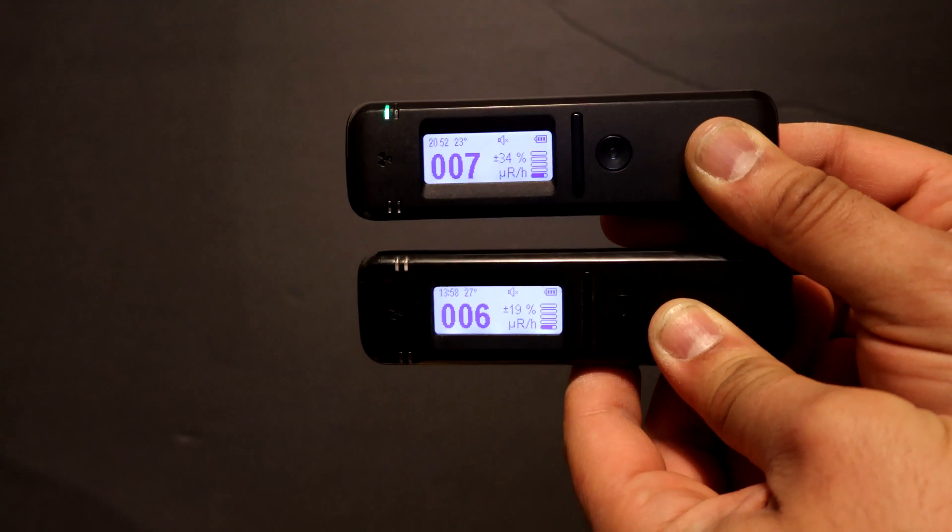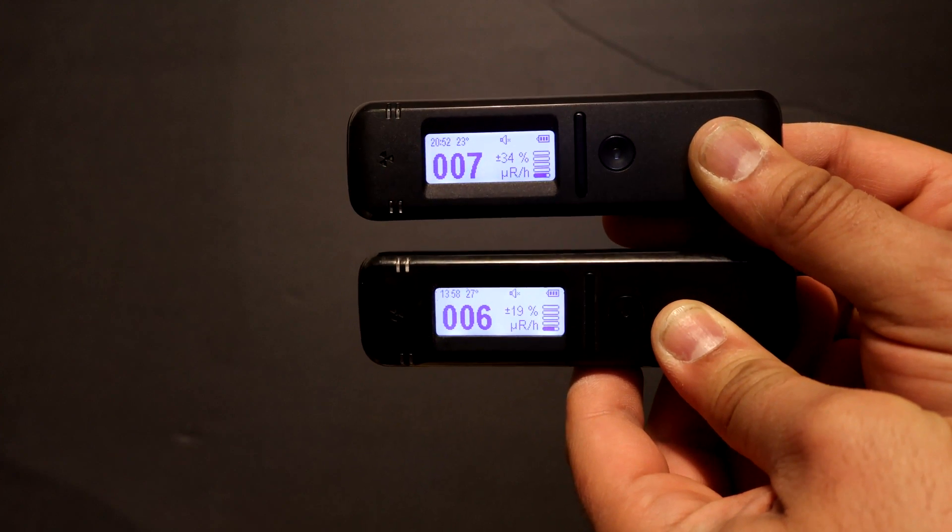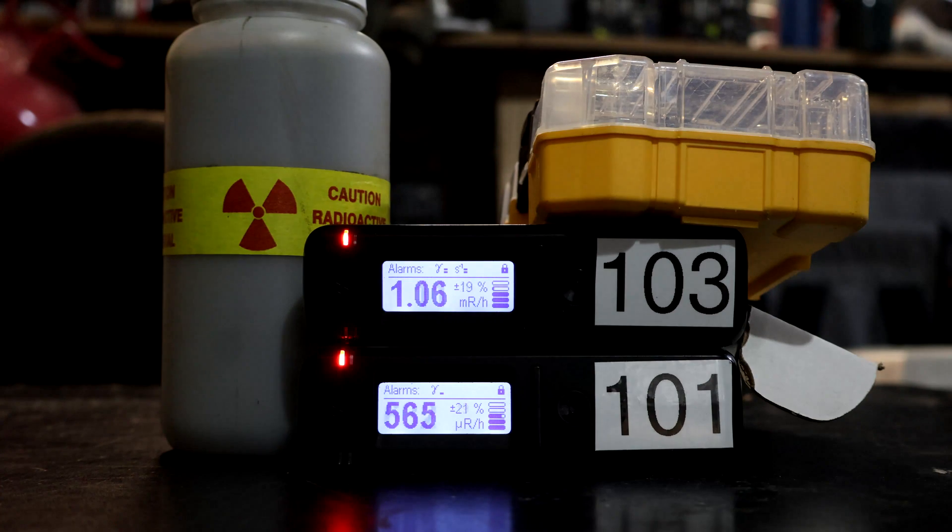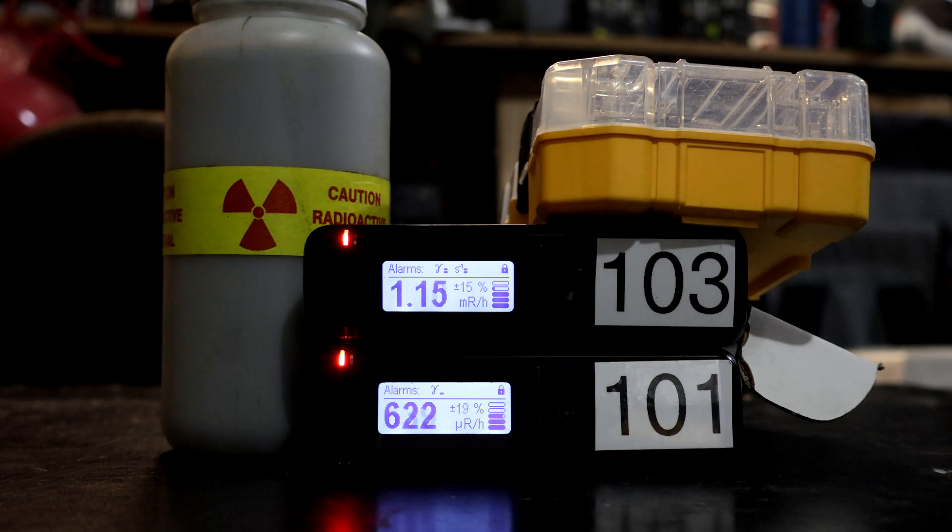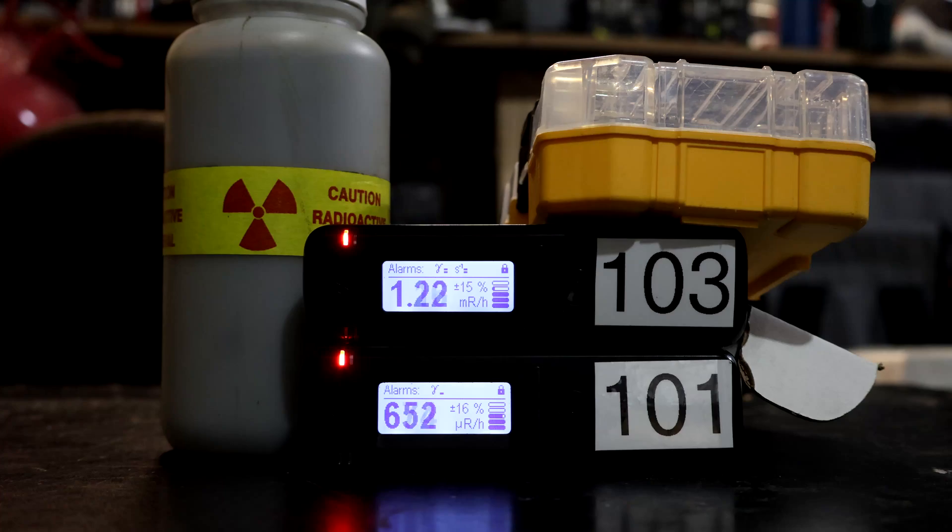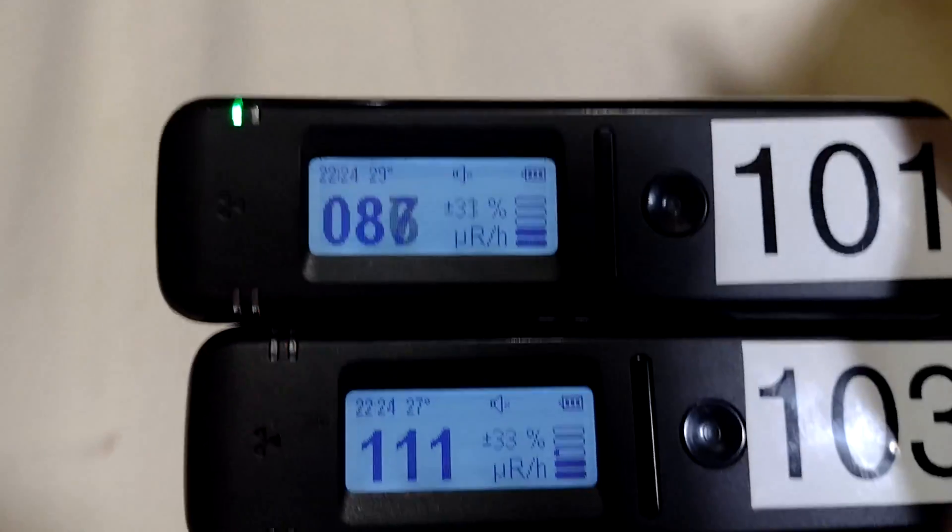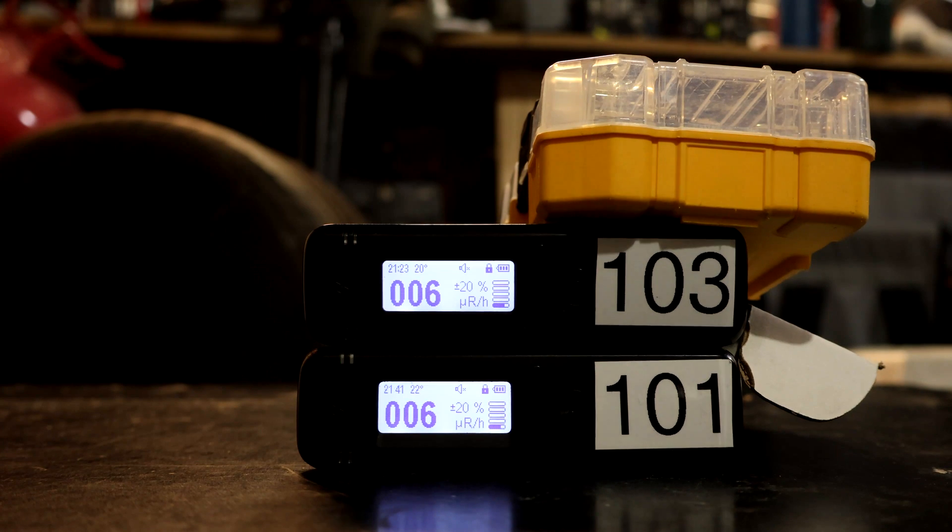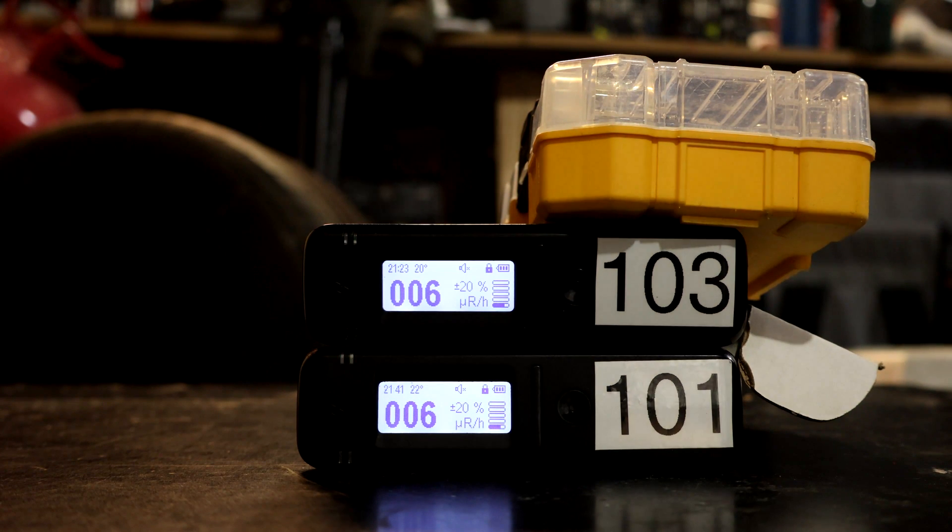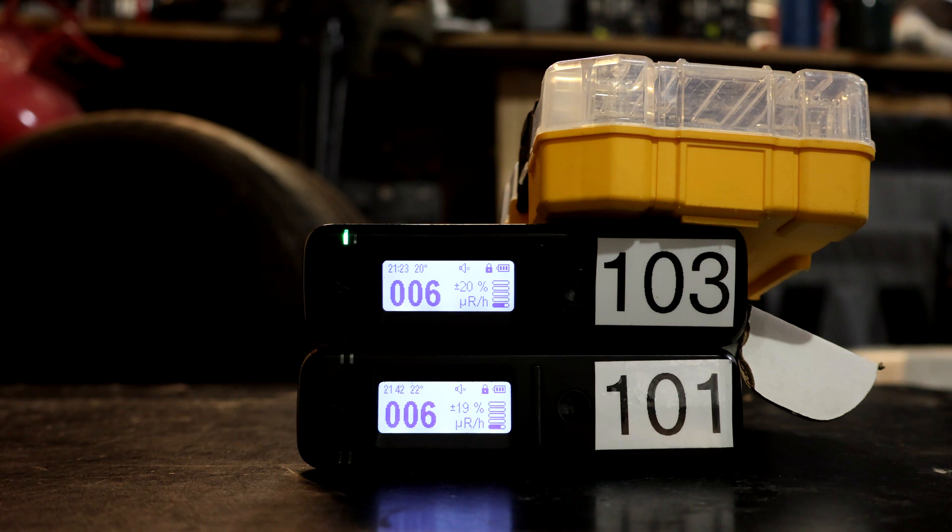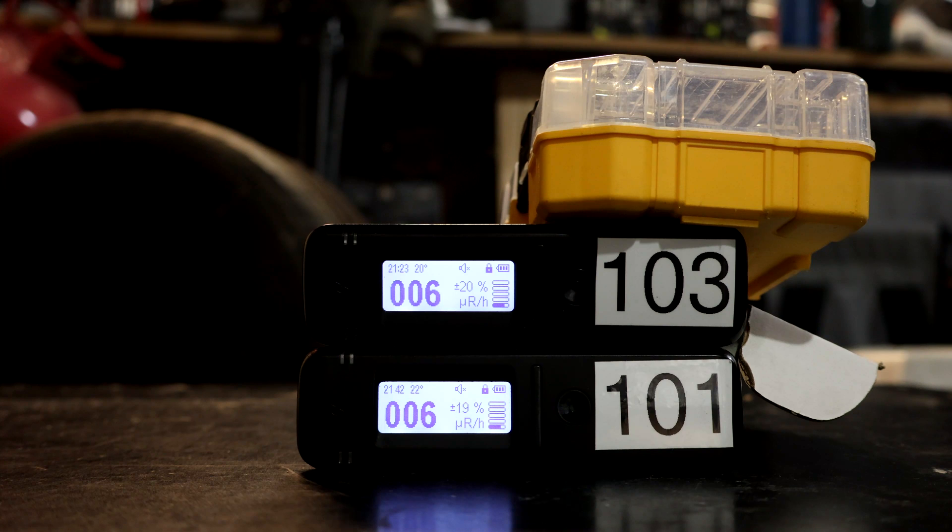The main difference of the 103 is the sensitivity. I consistently measured higher level of radiation with the 103 compared to the older 101 while the background remains similar. The 103 uses the same 10x10 cesium iodide crystal and the higher sensitivity, I am told, is achieved electronically.